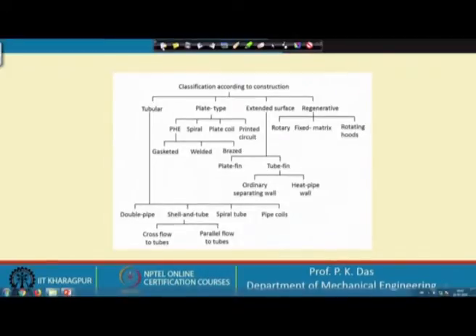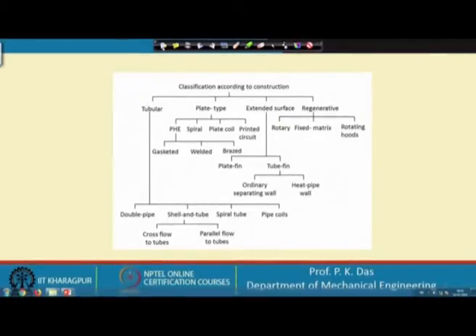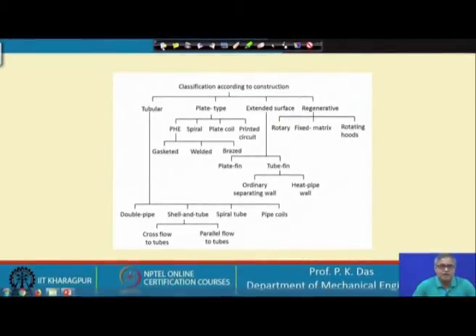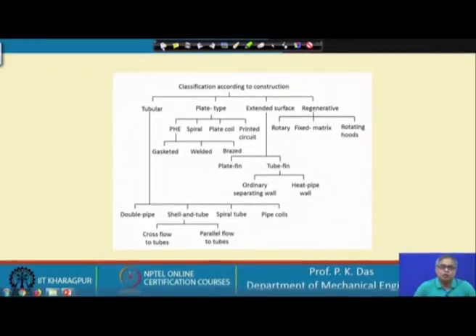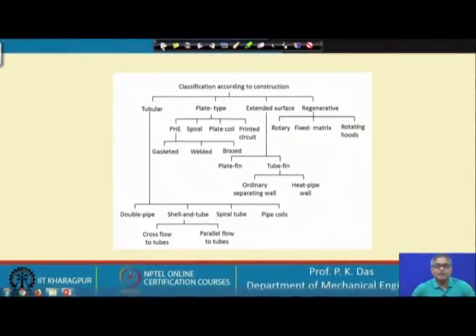Generally — though not without exception — tubular heat exchangers are preferred when both sides carry liquid. Tubular geometry can withstand higher pressure, which is an advantage since liquid flow often involves high pressure. Tubular geometry also provides very good sealing, so liquid leakage is not a problem. That is why tubular geometry is preferred when there are two liquids.